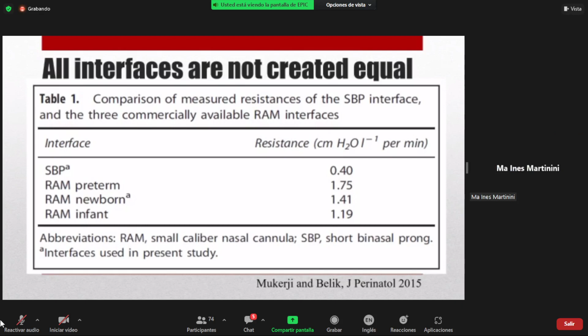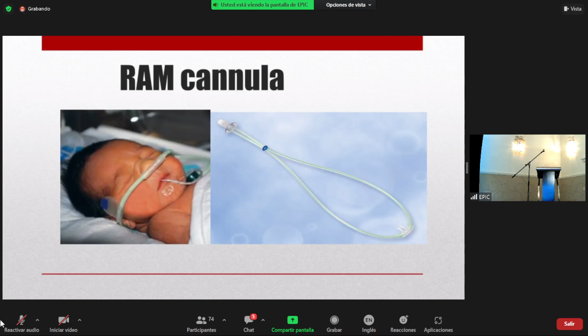It was approved as a high flow cannula, but it's been heavily marketed as a CPAP device. So it's stuck in the baby's nose, but they're careful to tell you you should not totally occlude the nares here. This is where it attaches to the ventilator circuit, and this long segment of tubing. There's no expiratory limb, so it's a one-way flow. It really works like a high flow cannula.